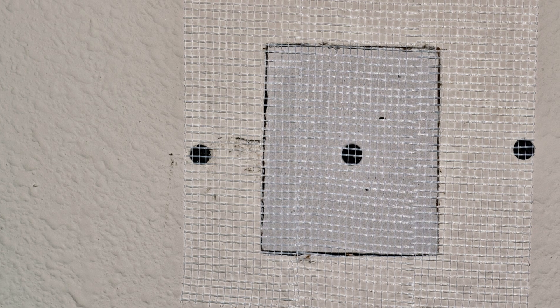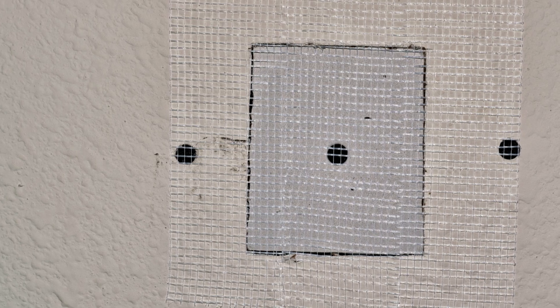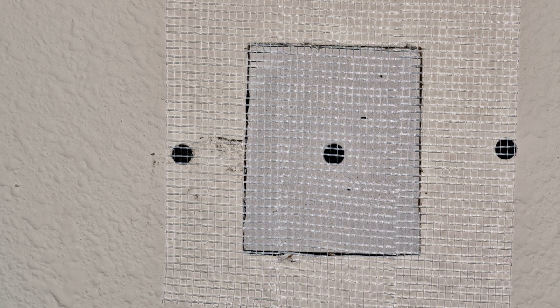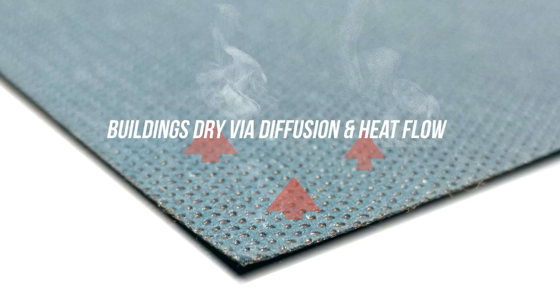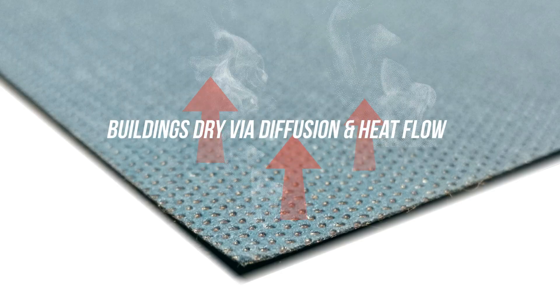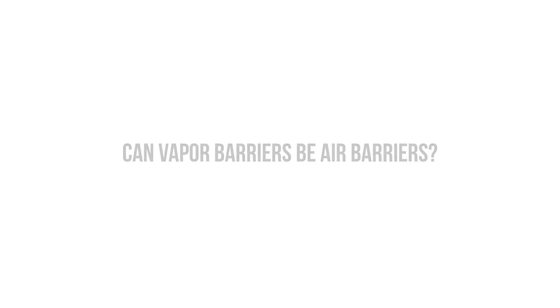By simply sealing that hole so that it's airtight, we can drastically reduce the amount of moisture passing through the walls by 99%. We've all heard the phrase 'buildings need to breathe,' and there's a lot of confusion around what this means. Buildings need to dry — people need to breathe. Buildings dry primarily via vapor diffusion and heat flow, and they get wet through air leakage.